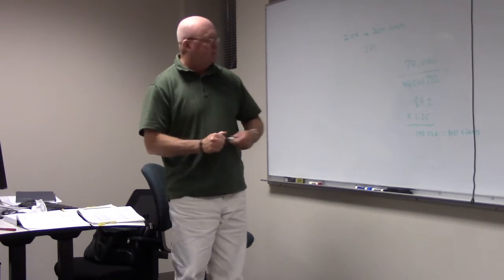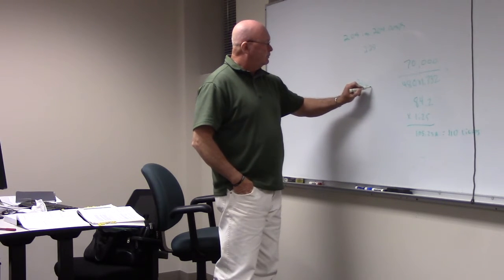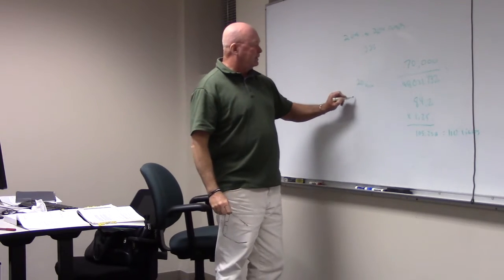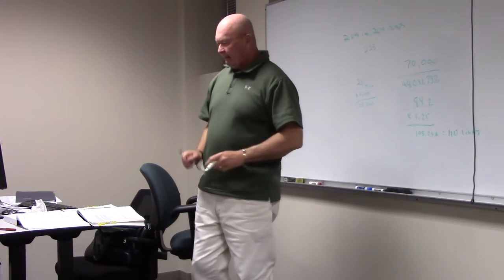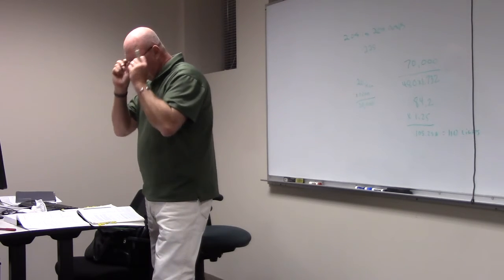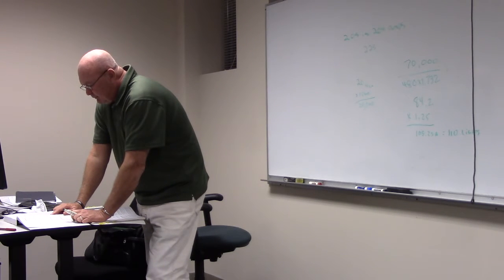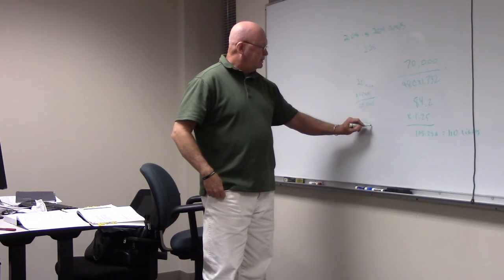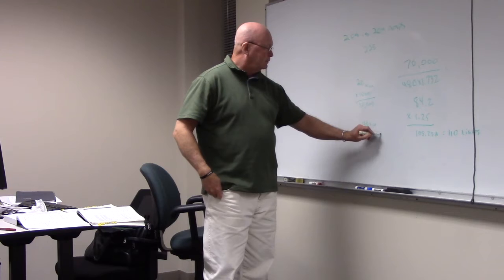Feeder supplying the water heater. The water heater, it said it was what? It just said it was 20 kVA, didn't it? Yes. And so 20 kVA is how much? 20,000. Okay? So we just want to leave that there for now. 220.51 permits the feeders on the electric space heating to be 100%. We had some space heating. So 40 kVA space heating is how much? 40,000, which is what it shows in the book.